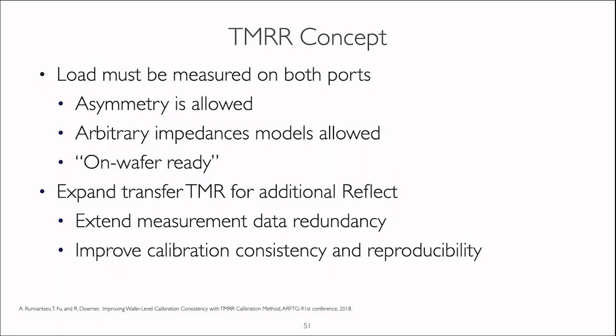This is a typical case when we make on-wafer calibration standards, when you have one parasitic of the stub on port 1 and another parasitic of the stub via stub on port 2. So basically the custom-made load is asymmetrical. Arbitrary impedance models are also allowed, so the load can be an arbitrary impedance element, even with the load resistance on port 1 and port 2 different from each other, which typically corresponds to on-wafer custom calibration standards. So this algorithm is on-wafer ready.